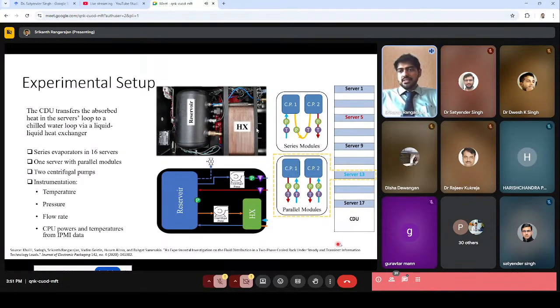So this is the coolant distribution unit, and you can see that there are different servers from server 17 to server 1, and we did instrument all of these, but I'll be showing results for these 5 servers. One thing is that as we move to the top of this rack, the hydrostatic pressure also changes. Since the hydrostatic pressure changes, the saturation temperature of the fluid received by each of the servers can change, which can really change the pattern in which each of these boil, because the server power and the server's workload, everything remains the same. But because of the hydrostatic pressure difference, the coolant enters each server at a different inlet condition.